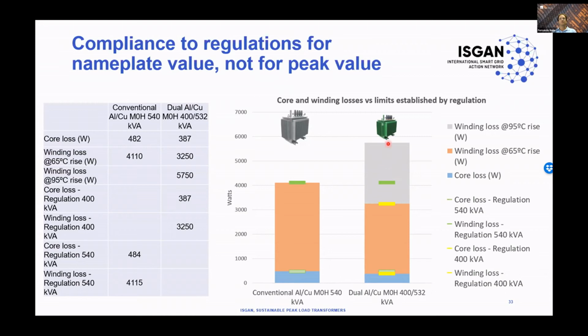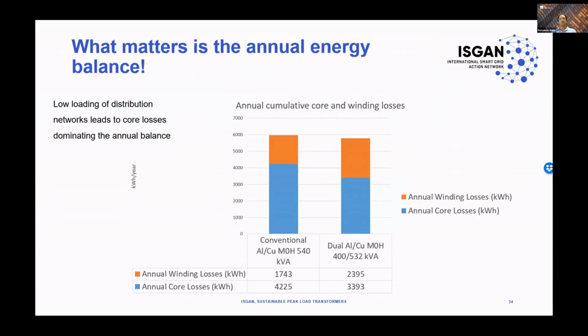So we could say, wow, this unit is not really fit for the European regulation. But actually, what we should care about is the total energy losses on an annual basis. So for low loading of distribution networks, the low loading leads to core losses dominating the annual balance. As we can see here in blue, these are core losses, and this is what dominates the annual balance. So what matters is to reduce core losses, to reduce more core losses than winding losses.